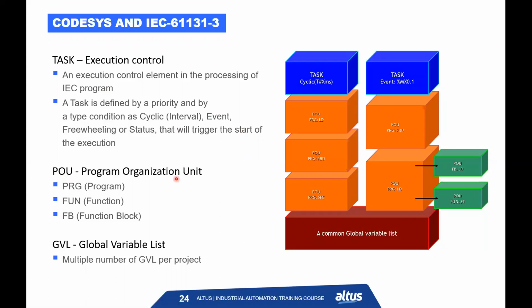POU, Program Organization Unit. So we can write here, for example, a POU in ladder, functional block diagram, and sequential function chart running in this task. And here we have a second task inside the same one. You can imagine that this is a PLC. We can have a second task running as an event, receiving an outside trigger to run this other program organization unit, which is the same as the subroutines in the older concept. And of course, a database that we call the global variable list, which can be accessed from every one of these subroutines.